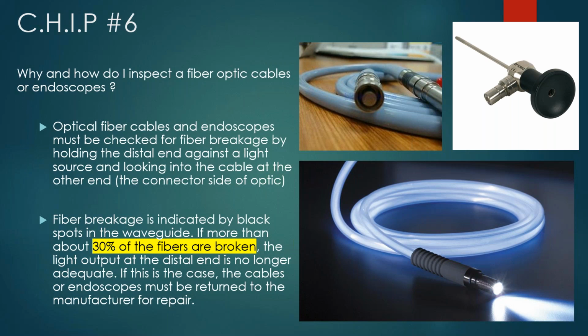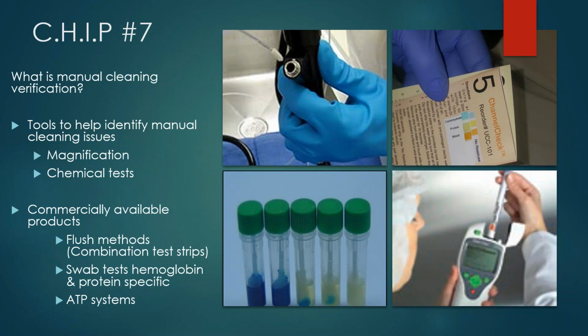If more than 30% of the fibers are broken, the light output at the distal end is no longer adequate. And if this is the case, the cable should be returned and repaired or replaced. Really what it causes the surgeon and the staff in the room to do is just crank that light source way, way up to try to compensate for the broken fibers. And that's really not what we want. So that's a quick and simple thing to do to make sure they're getting what they need.